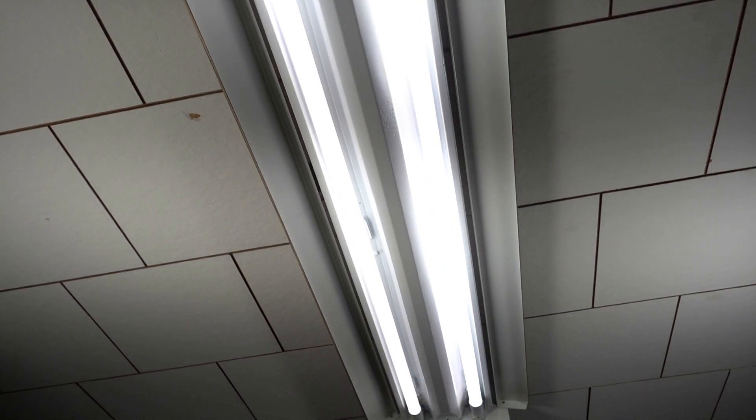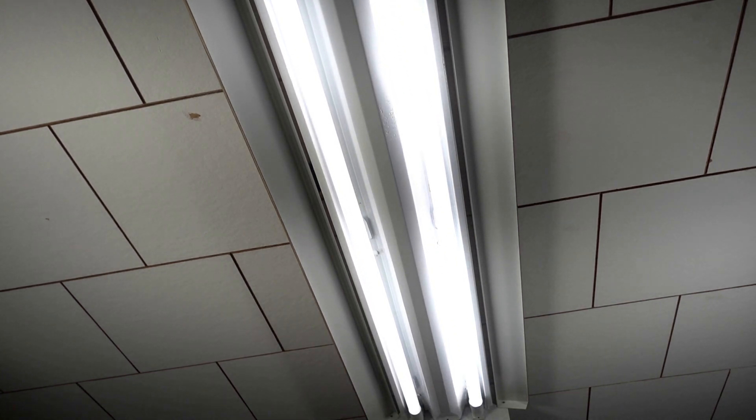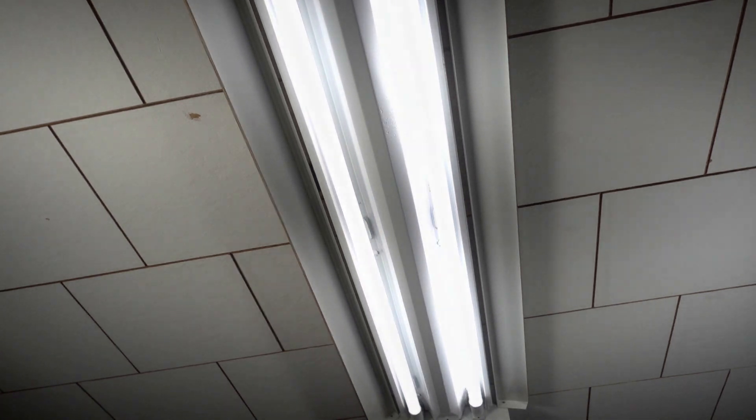I got both fixtures working, and I noticed something peculiar. The tube on the far side is not as bright as the one on the right side. First, I thought it might be defective LED tubes, but I swapped them, and it's still dim. I think it's a function of having the wiring go through the ballast. So I think I'm going to have to bypass the ballast and see if they're any better. I hate to do this. It's a lot more work.